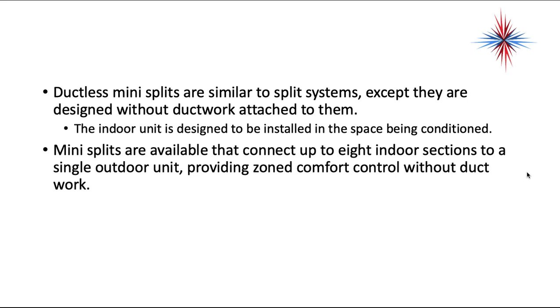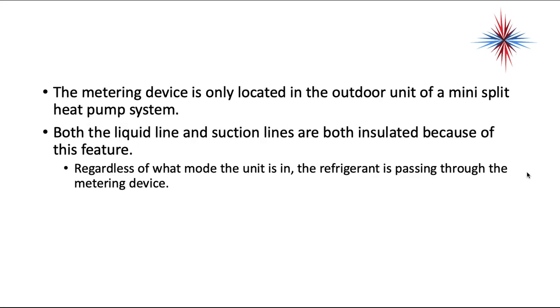Ductless mini splits are similar to split systems, except they're designed without ductwork attached to them. The indoor unit is designed to be installed in the space being conditioned. Mini splits are available that connect up to 8 indoor sections to a single outdoor unit because they provide zone comfort control without ductwork. The metering device in a ductless system is only located in the outdoor unit of the mini split heat pump system. Both the liquid line and the suction line are insulated because of the single metering device.